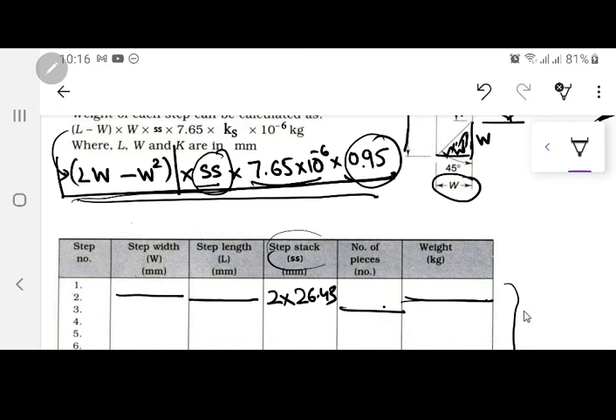But this is only for 0.27 mm. If you have a greater thickness of sheet, there will certainly be a different table or graph, and it will be on the higher side, because more thickness means more eddy current losses, more watts. This is watts per kilogram, so this is actually for the eddy current losses.